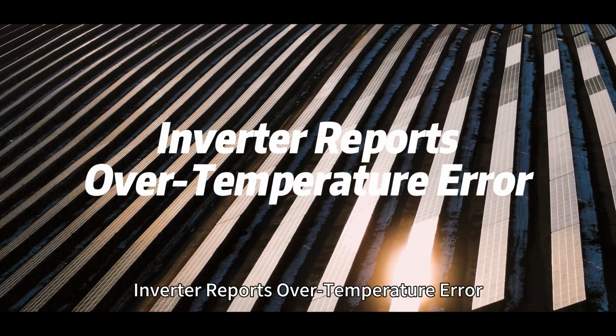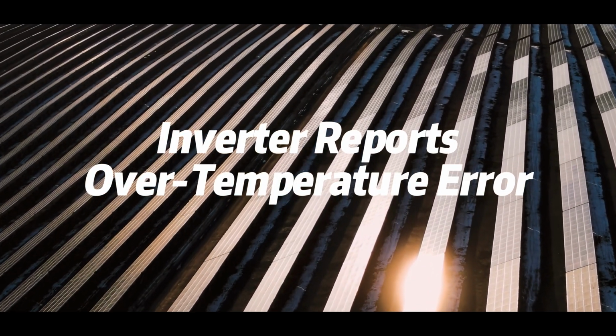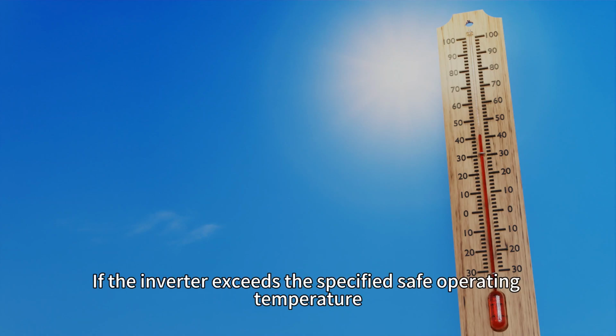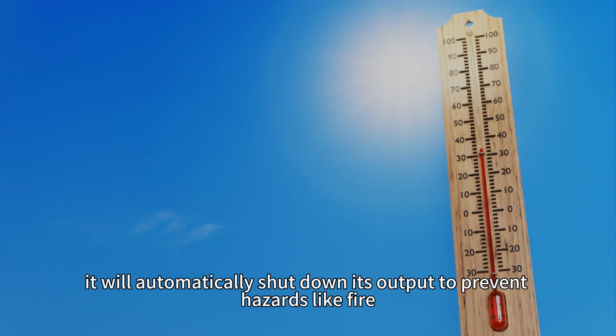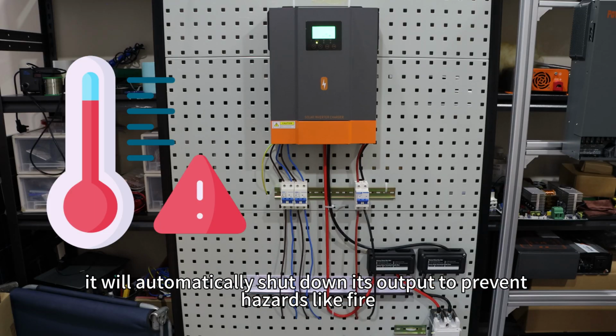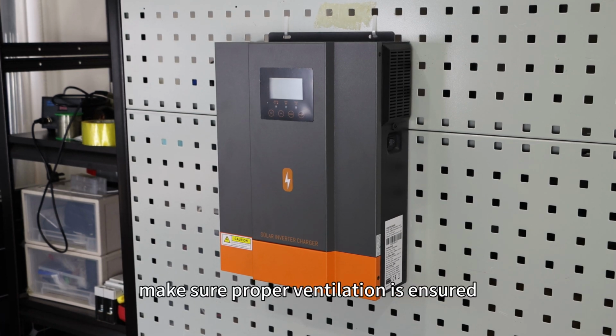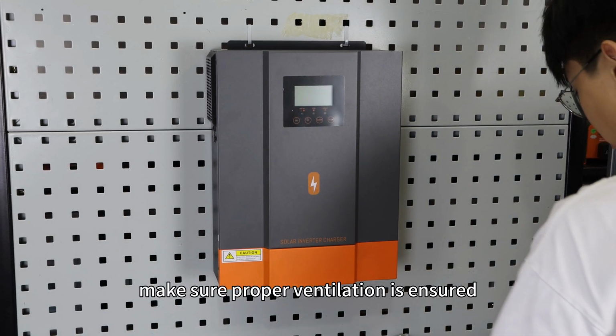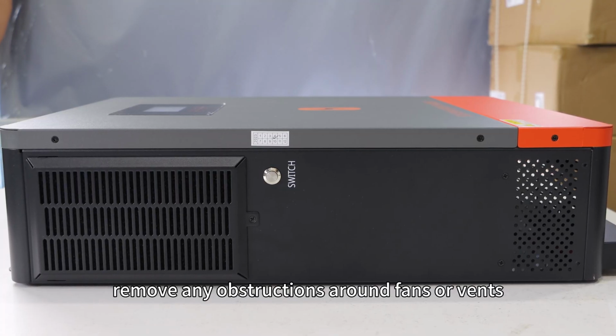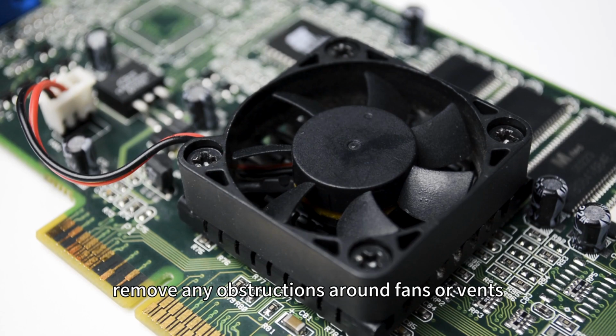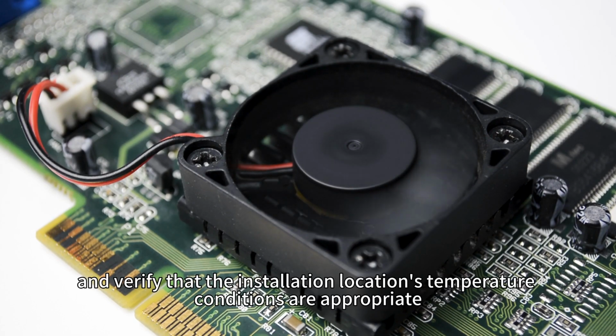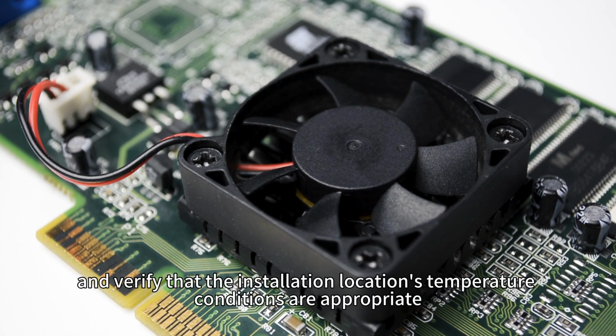Inverter reports over temperature error. If the inverter exceeds the specified safe operating temperature, it will automatically shut down its output to prevent hazards like fire. To address this, make sure proper ventilation is ensured, remove any obstruction around fans or vents, and verify that the installation location's temperature conditions are appropriate.